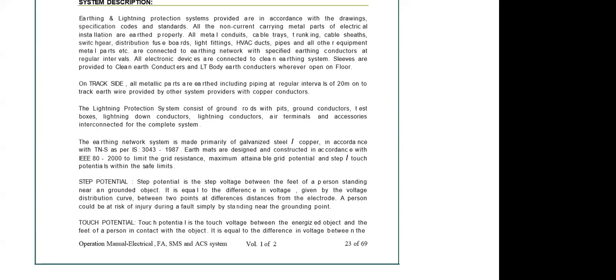Here, two points I want to mention: as you see here, these are called step potential and touch potential. The step potential is what? It is the step voltage between the feet of a person standing near a grounded object. It is equal to the difference in voltage given by the voltage distribution curve between 2 points at different distances from the electrode. I will explain this with a simple example.